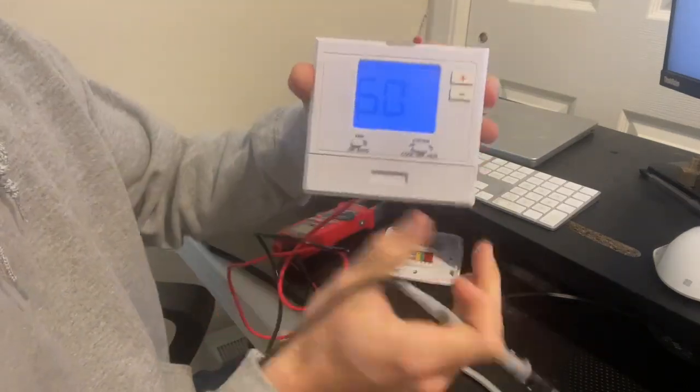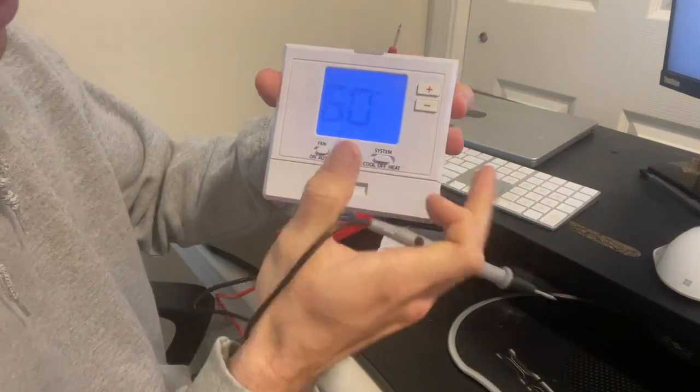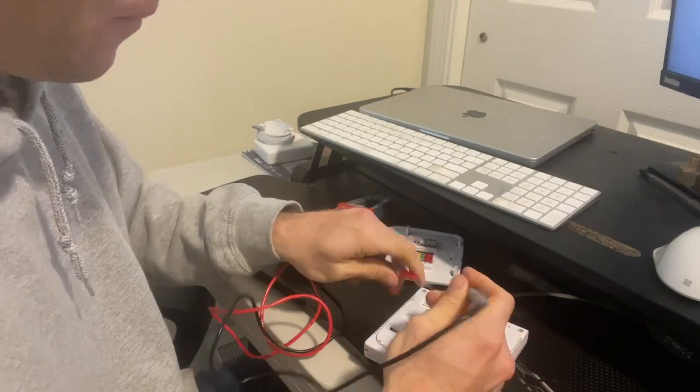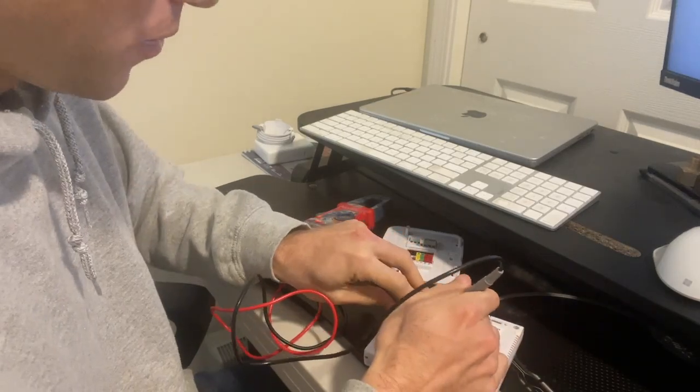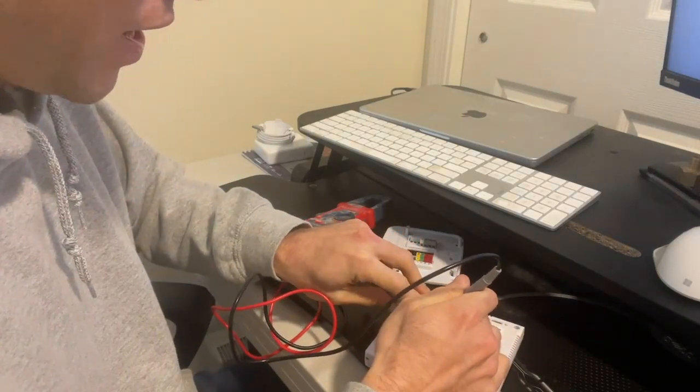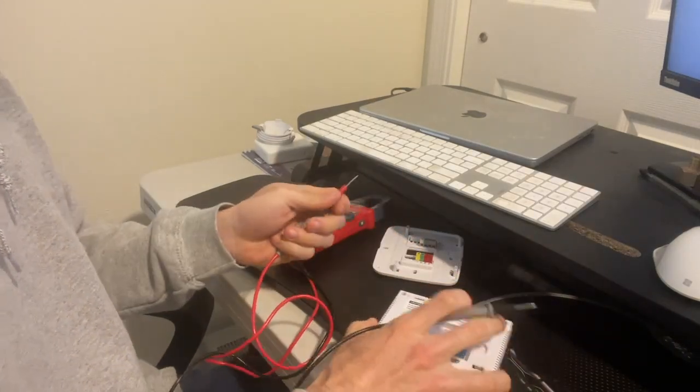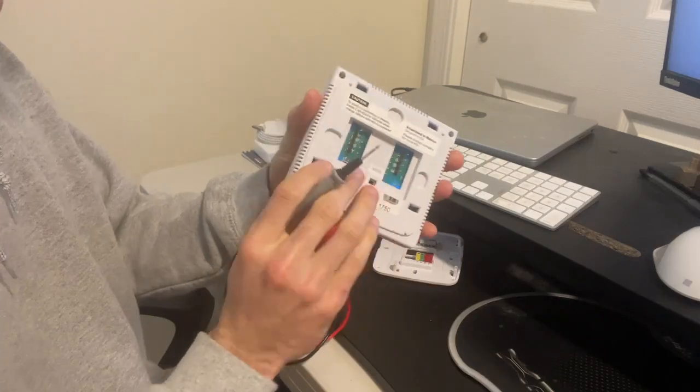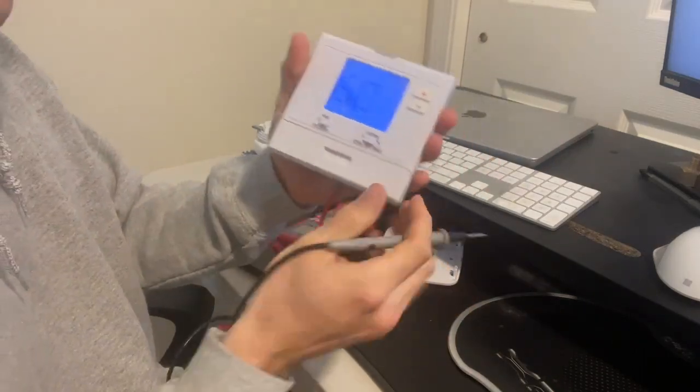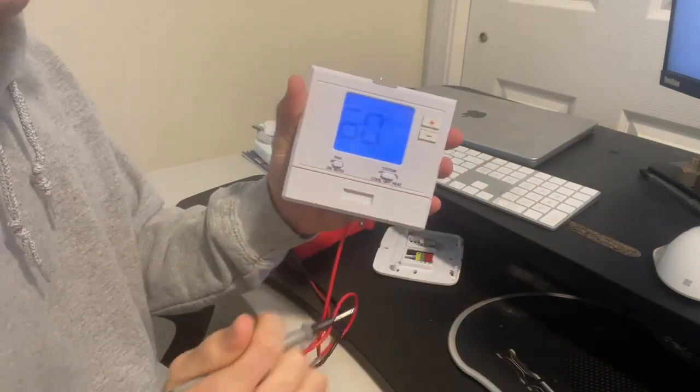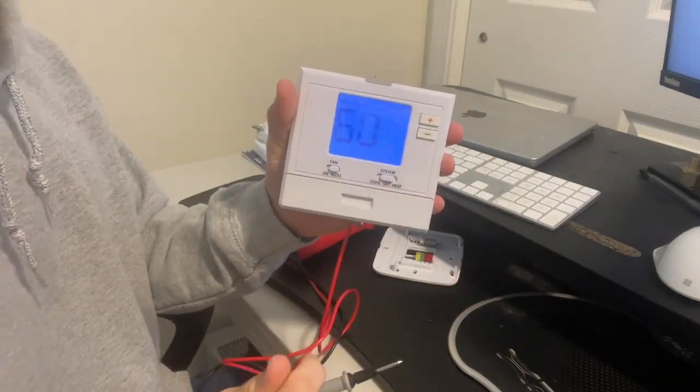And then when I set the fan to be off or auto, I'm going to lose that connection that we just had on the circuit board. So that is how you can verify that your thermostat is working as expected.